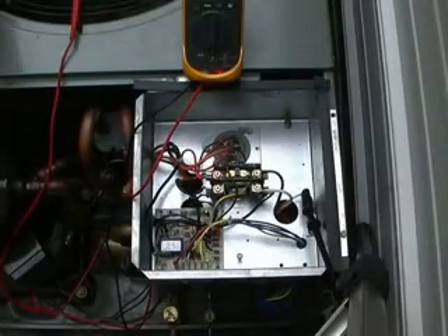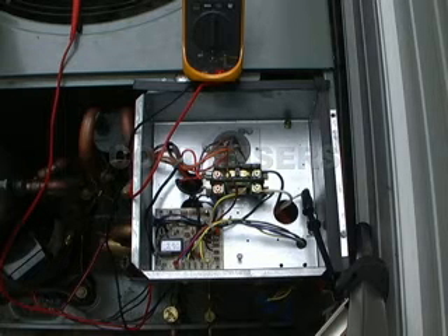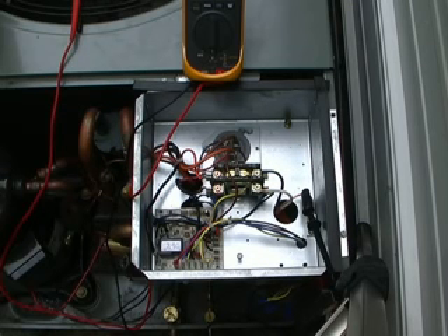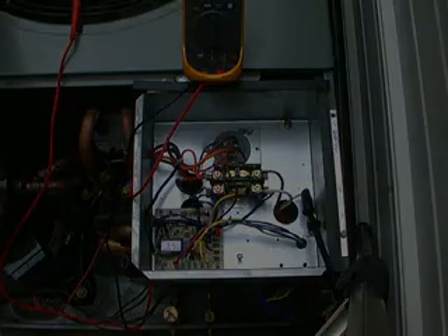Okay, let's troubleshoot some of the common electrical problems with this Rheem unit we have here. Of course, the most common symptom when you go on service calls for electrical problems is that the condenser unit's not running. So immediately you have two possibilities: the contactor's pulled in but there's no high voltage, or the high voltage is there but the contactor's not pulling in.